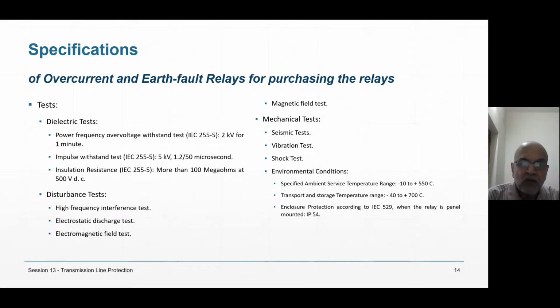Impulse withstand, 1.2 by 50 microsecond, 5 kV. The relay should not be damaged. Insulation resistance more than 100 megohms. Disturbance test, high frequency interference test, electrostatic discharge test, electromagnetic field test, mechanical test, seismic test, vibration test. You have to deliberately vibrate the relay and see that it is not damaged.